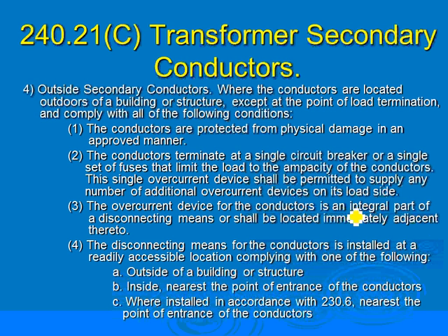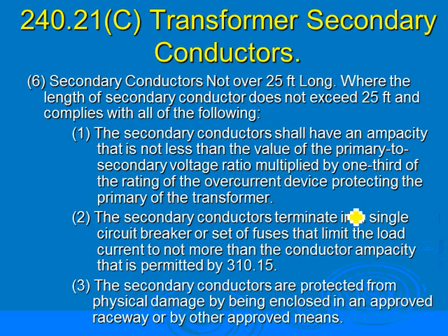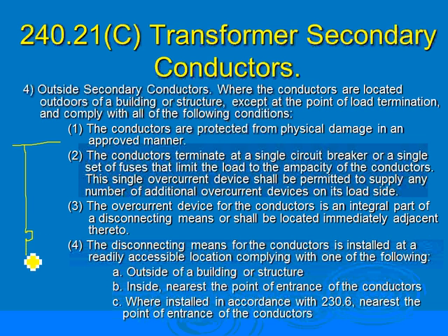It gets even more interesting if you have outdoor transformer secondary conductors, not in a building or structure except at the point of load, and the conductor is protected from physical damage. Do you see any limitation on how far you can go outdoors? That's what I see. If you're doing things outside, like overhead conductors, when you tap conductors you're not concerned with overload. So with transformers, outdoor conductors: if I'm pulling things outdoors, guys, I can have a conductor here with no limitation. I can tap a load here from this conductor, I can tap another load. Everything is outdoors, right? And I tap another conductor from here.